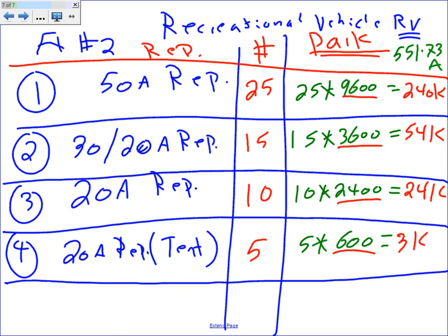Okay, so that's easy. And I want you to add all these tenths and locations. Add these: 25 plus 15, 30, 40, 50, 55, right? These are 55 sites. When you do your 55 sites, then you're going to go to the derating factor for 55 sites. And the second thing, can you guys add all these KVAs together now? Add all the KVAs. 1053. No second?